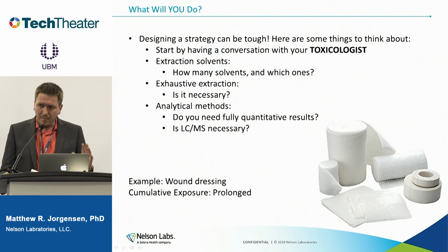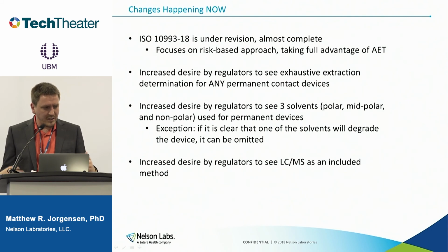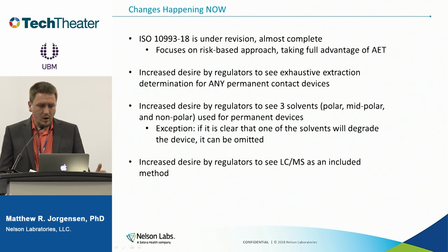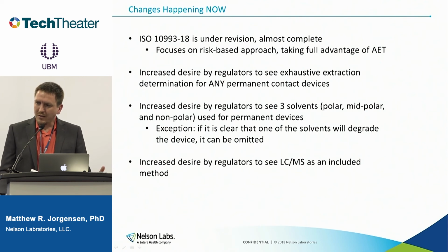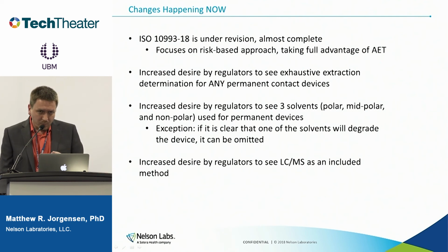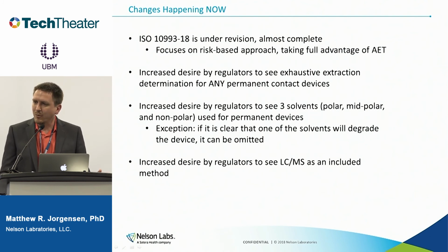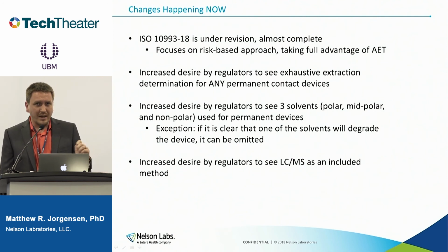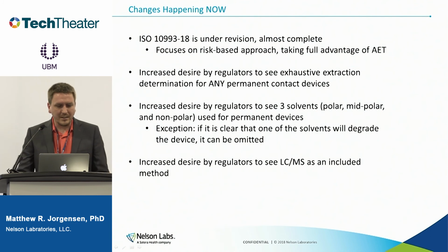So I mentioned some of the things as I was going along that we see changing now. One of the things really important to note: ISO 10993-18 is under revision. There's a lot of things in there that are changing. I see a lot of what I consider improvements to the draft. We hope to have this out soon, though I guess we've been hoping that for a little while, but I think we're close. We really focus on a risk-based approach. This concept of an analytical evaluation threshold is really prominent in this draft. It means that we really only need to care about looking for things that might have a toxicological consequence. I think that makes a lot of sense.